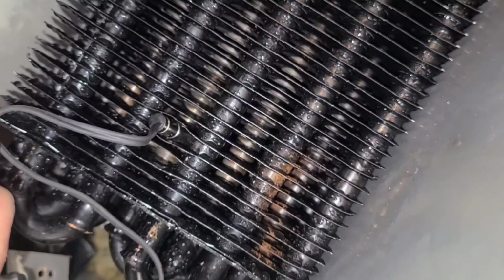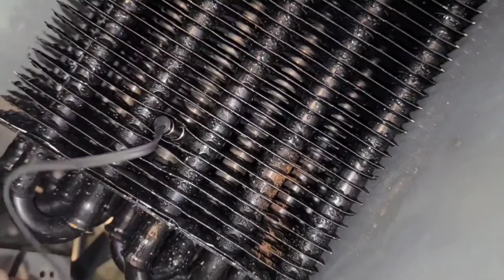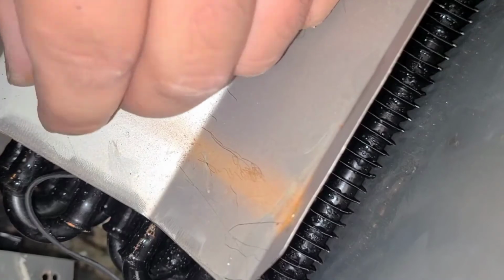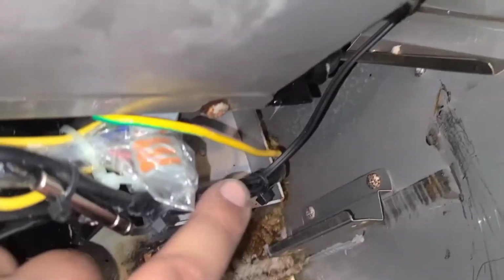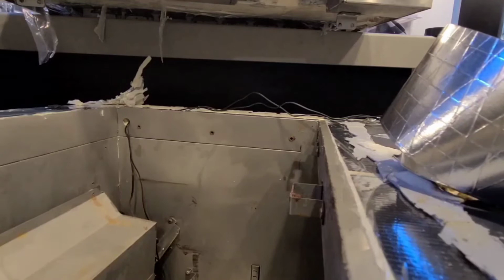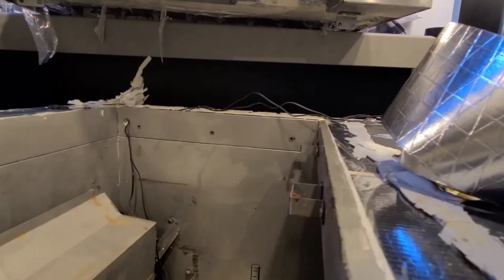Just trying to make sure that new sensor is in there nice and tight, nice and snug. There you go. Secure with the zip tie. Make sure the wire's not getting pinched by the cover. And then there's my room temperature sensor nice and secured. Make sure everything's secured before I start closing anything up. So there's a little groove inside the foam insulation for the leads. So I'm just gonna put some tape right there just to secure them. That way when I put the top down, I'm not gonna risk pinching or moving the wires anywhere.